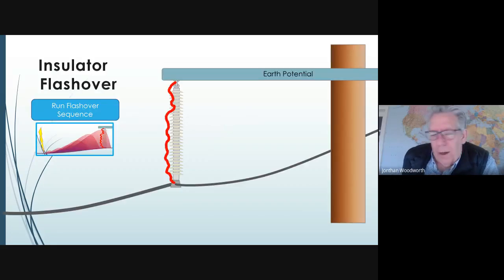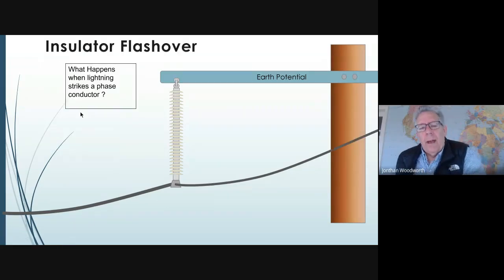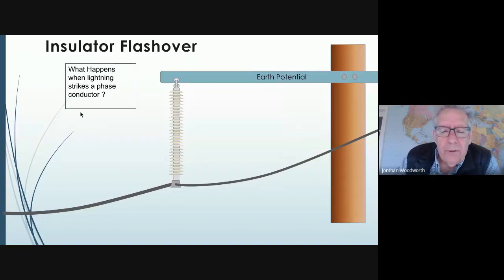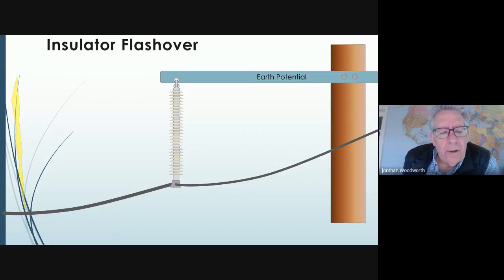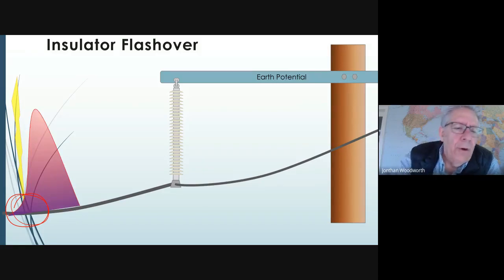I have a couple of animations here that should give you a better idea of what happens when lightning strikes a line. In this case, we have a power system line that's just unprotected. There's no shield above it, and lightning comes along and can strike the line. And when it strikes the line somewhere on the line, there's no telling where it's going to strike. It doesn't prefer one point over the other. It sets up a voltage on this line. So lightning is actually a current source. So we usually measure lightning by how much current it sends into the system.